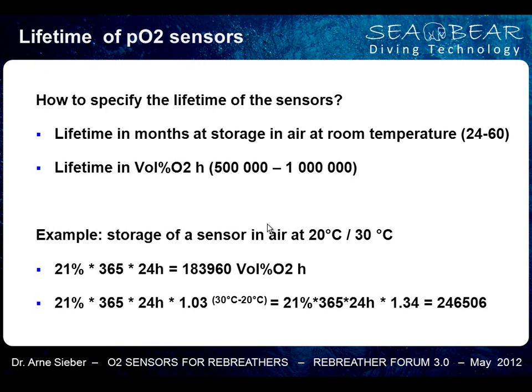So what does this unit mean? You multiply the oxygen fraction in which the sensor is stored with the amount of time. As an example, storage of a sensor in air for 1 year: 21%, multiplied by 365 days, multiplied by 24 hours, gives us this amount of volume percent oxygen hours. If we use this sensor now at a higher temperature, we have learned before that for each degree centigrade we have an increase of about 3%. So we can say 21% multiplied by 365 days, by 24 hours. But now we have this small part here.